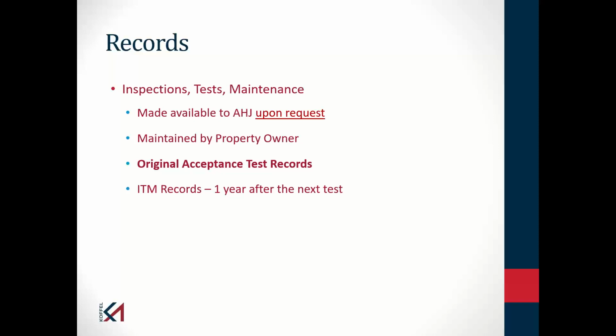So within NFPA 13, there are requirements for an above-ground piping certificate and an underground piping certificate. It includes information about the system and what tests were performed. The contractor is required to give that to you upon acceptance of the system. NFPA 25 says you should have that documentation. And again, that is useful documentation to determine what tests were done. So if I have a sprinkler leak in a coupling, was a hydrostatic test done upon acceptance of the system? Or what tests were done on an annual basis to verify that the system was in proper operating condition.